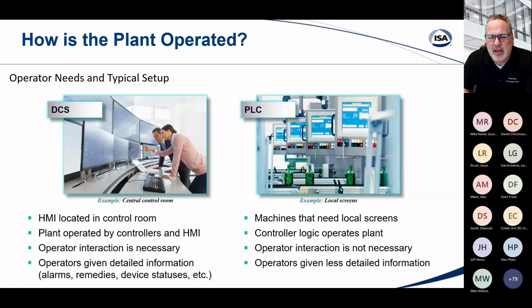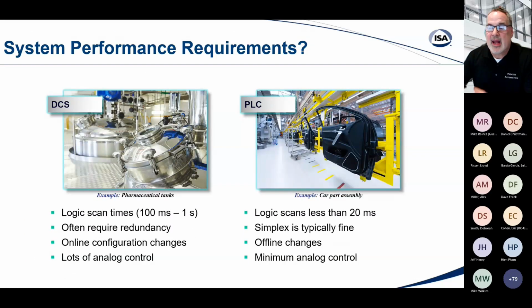Generally speaking, the HMI screens give him limited information, just enough that he can run and operate the plant. If there is a fault, he might get a quick indication of it, but he probably wouldn't be able to dive down and find out exactly where that failure came from within the plant, because it's probably more unit-based control. Again, I'm speaking in very general terms. I'm sure Grant could sit there and say, no, we could do all that. And I'm certain that a PLC manufacturer can, but it's not designed that way right out of the box. So it has to be configured as opposed to just being developed that way.